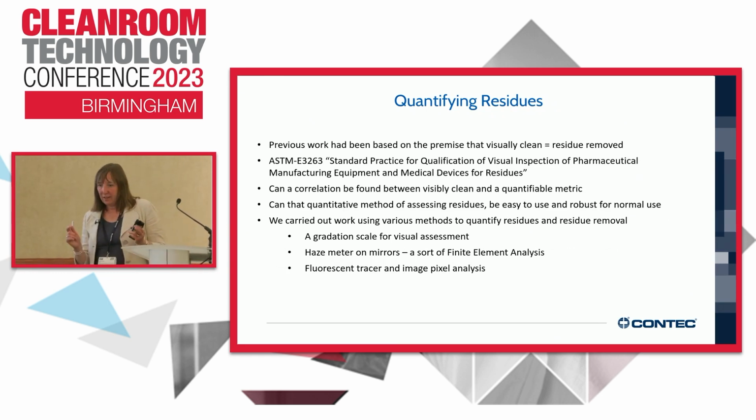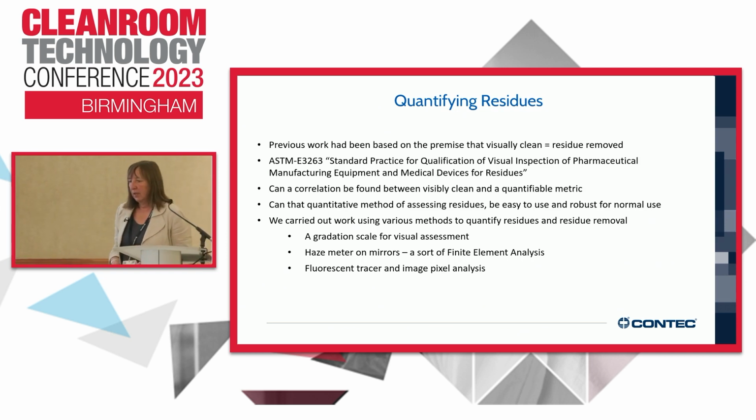So there is a standard, the standard practice for qualification of visual inspection of pharmaceutical manufacturing equipment and medical devices for residues. So there is a standard which you can follow. That's up there. But again, it's a visual thing, so it's very subjective. What somebody sees as being visually clean, somebody else might feel it's not.